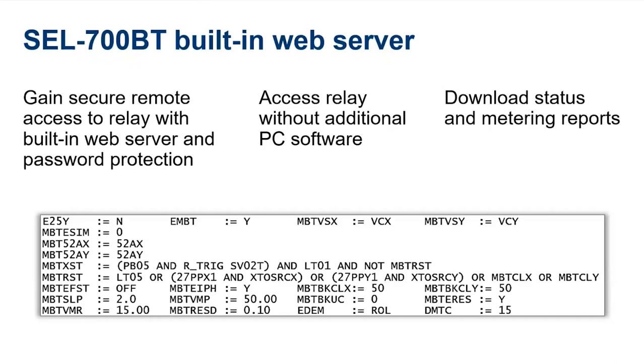On the slide here, the settings of the entire Modbus transfer functionality are shown. This is to show how simple it is to set this product, because these are all the Modbus transfer settings that you need to set to put this 700BT in the Modbus transfer application.